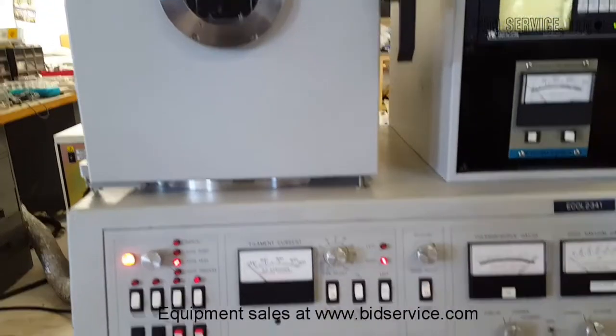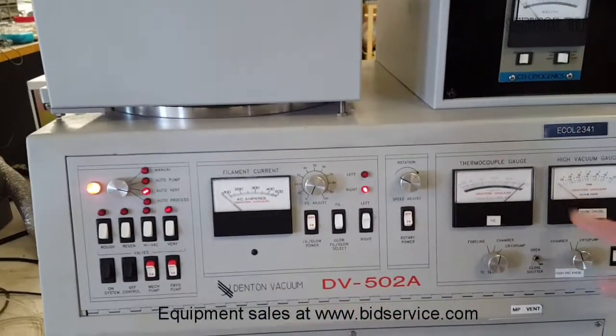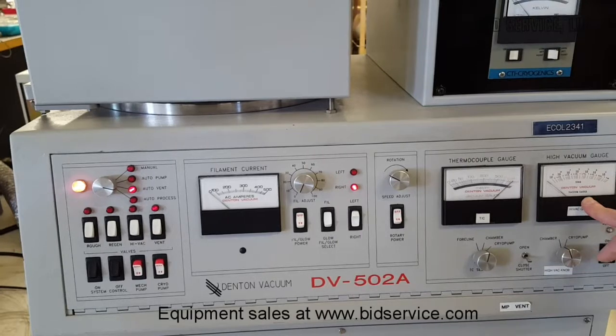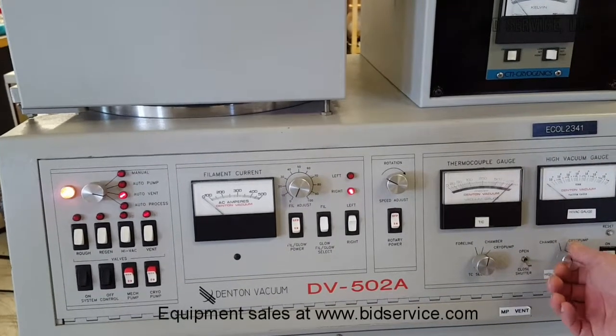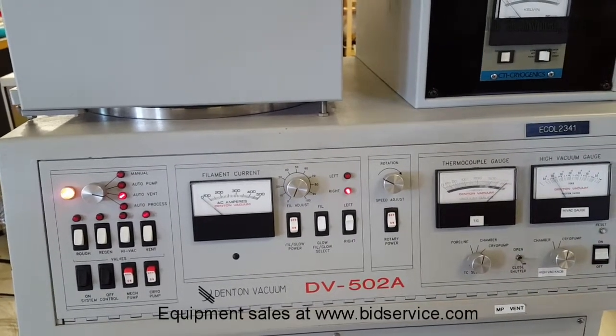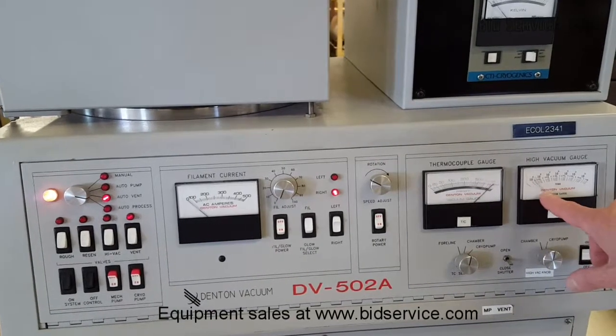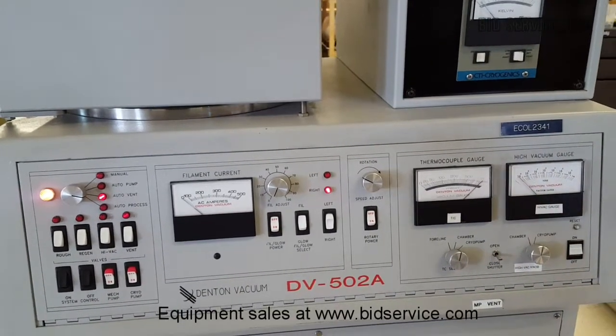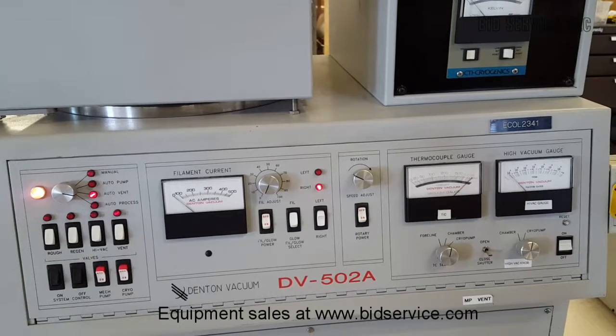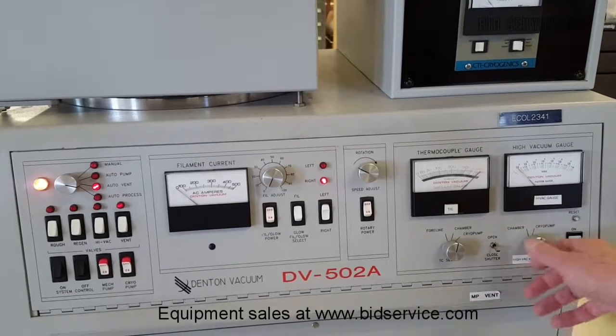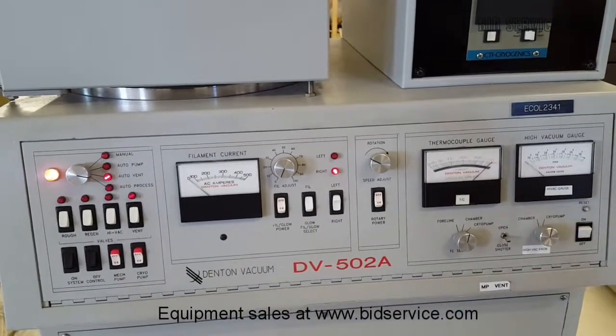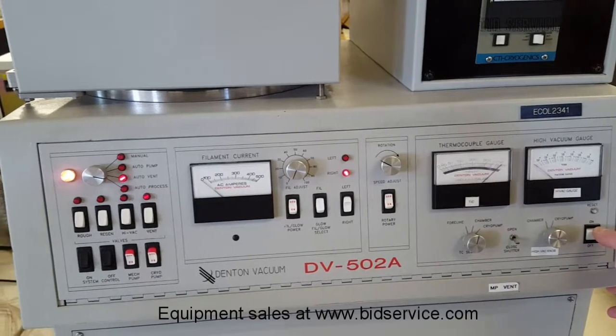You can see whenever the high vac is closed and you're looking at chamber, no power is being sent to the gauge, so you always get a 0 there, but you can always look at the cryo. It may take a little time to ignite the cold cathode. And then you can shut it on and off. That's the off one. Turn it back on.